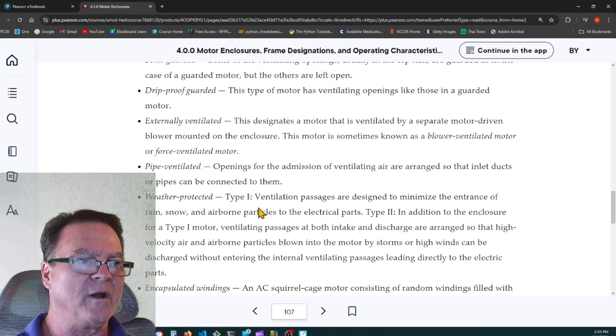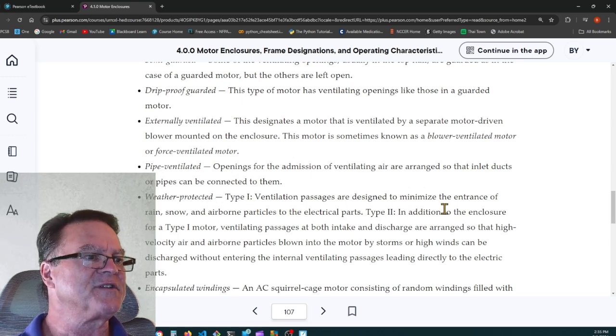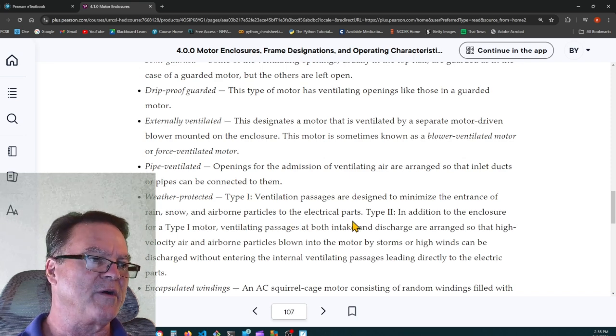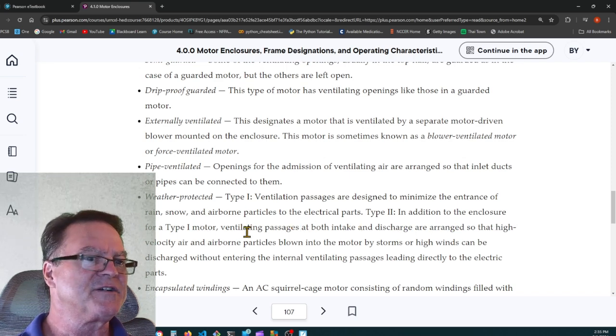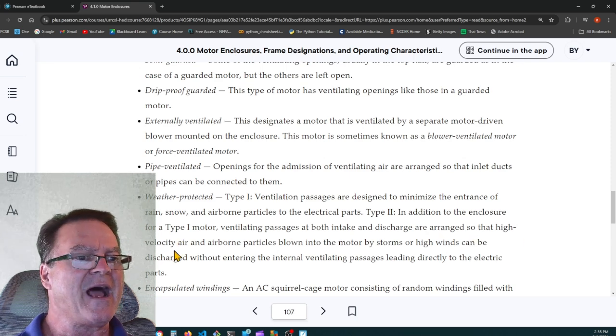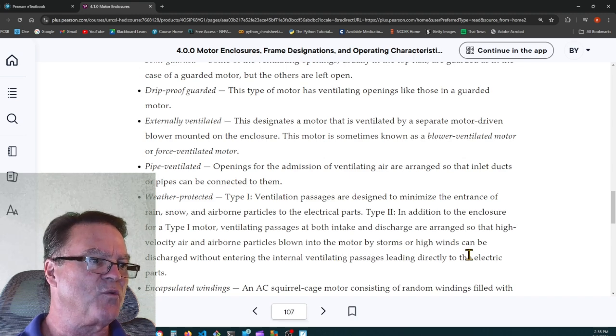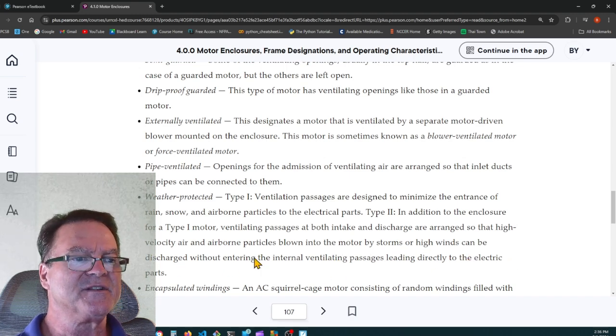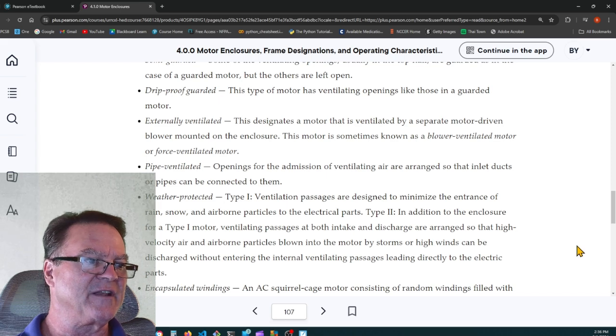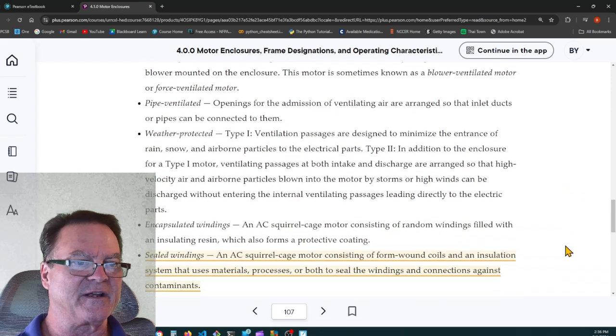Externally ventilated, pipe ventilated, weather protected. Type 1: ventilation passages are designed to minimize the entrance of rain, snow, and airborne particles to the electrical parts. Type 2: in addition to the enclosure for a Type 1 motor, ventilating passages at both intake and discharge are arranged so that high velocity air and airborne particles blown into the motor by storms or high winds can be discharged without entering the internal ventilating passages leading directly to the electric parts.